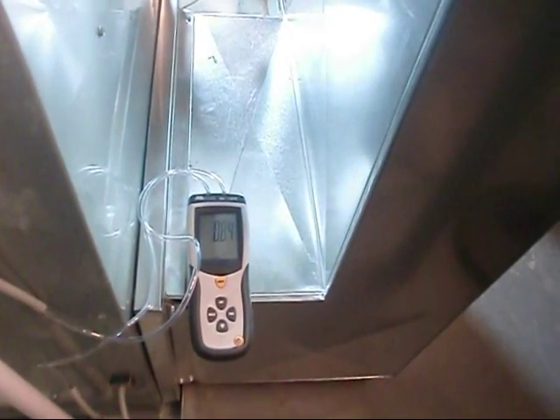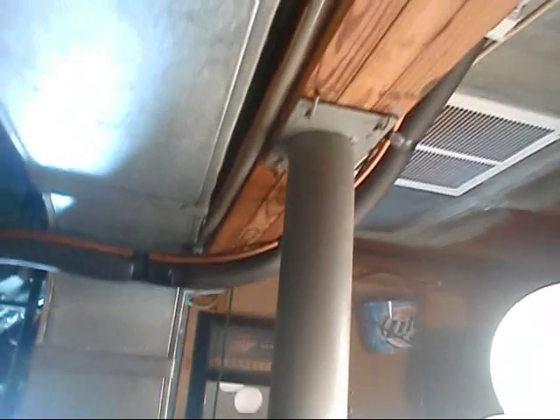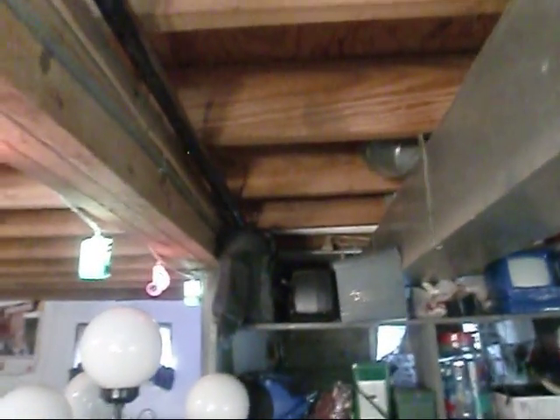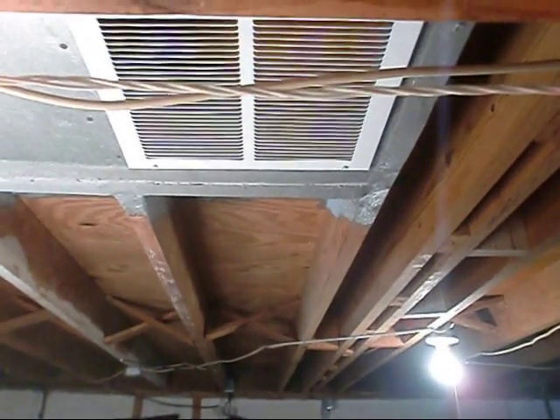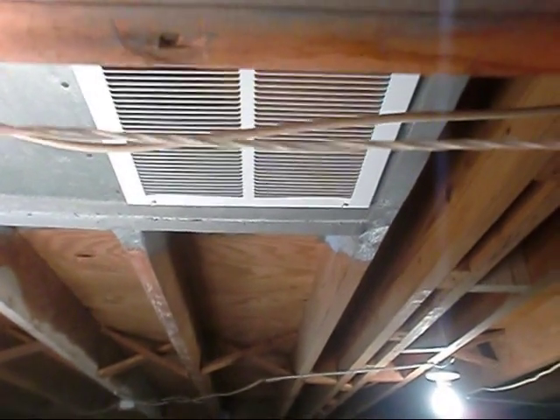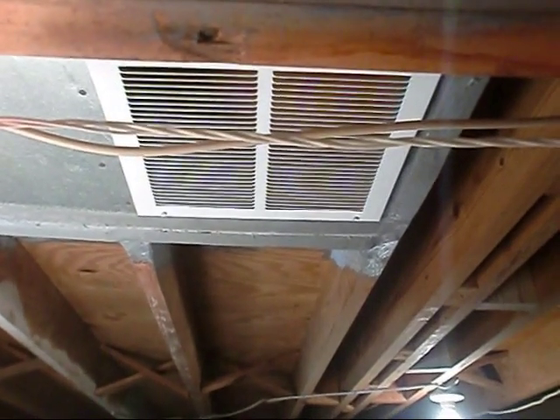There's really no point in even continuing going up. What we need to do is update the return here — I know we need to have that return going all the way down. I probably need to oversize the return. It looks like it's about an 8x8x10 there, coming off a 24x8 drop — I'm sure that's well under; I believe it was like two tons of return on my chart. Anyway, this will actually help me get my temperature rise down. Like my brother said, that's basically what we're really concerned about right now. We're getting ready to perform our temperature rise test — it's saying 35 degrees to 65 degrees, so hopefully we'll be within there. The limit goes out at 160.